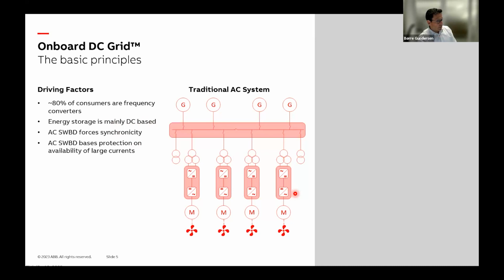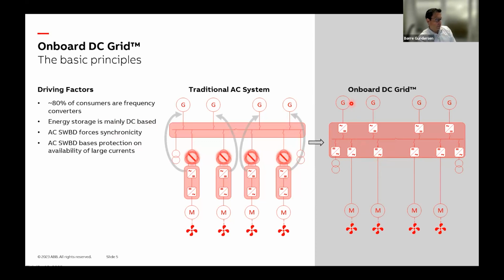With DC, we basically remove the transformers and take the rectifier out, rectifying at the input instead - so it looks like this. It's the same generator, the alternator is the same, but we rectify before we distribute. So you're not fixed to 60 or 50 hertz anymore, and each of these sources can be individually controlled on speed and load, which makes the combustion efficiency better.